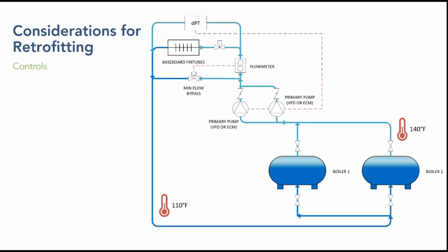Here's a kind of a concept of that. So this is a primary variable primary configuration. Your system pumps or your primary pumps are being controlled off of this remotely located differential pressure transmitter, but also you have this flow meter here which controls this bypass, which ensures minimum flow through the system, which can be the constraint, can be the boiler or the minimum flow through the pumps. But there's usually some minimum flow requirement.